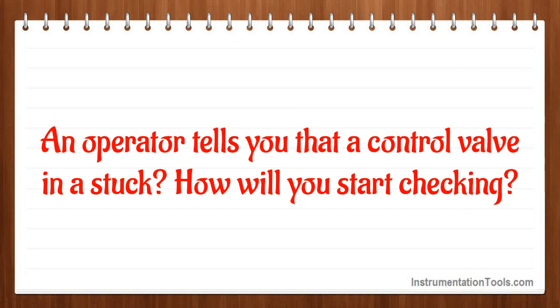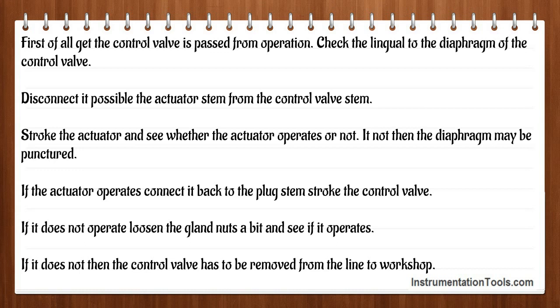An operator tells you that a control valve is stuck. How will you start checking? First of all, get the control valve bypassed from operation. Check the signal to the diaphragm of the control valve. If possible, disconnect the actuator stem from the control valve stem and stroke the actuator to see whether it operates. If not, then the diaphragm may be punctured. If the actuator operates, connect it back to the plug stem and stroke the control valve. If it does not operate, loosen the gland nuts a bit and see if it operates. If not, the control valve has to be removed from the line to the workshop.